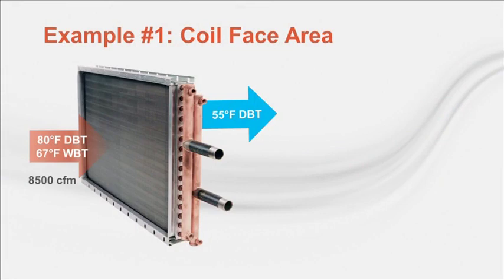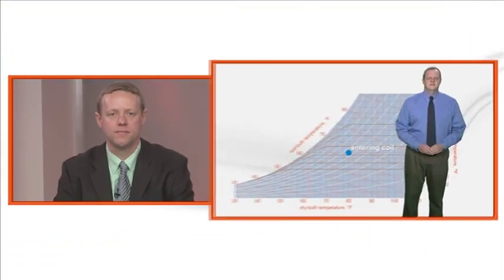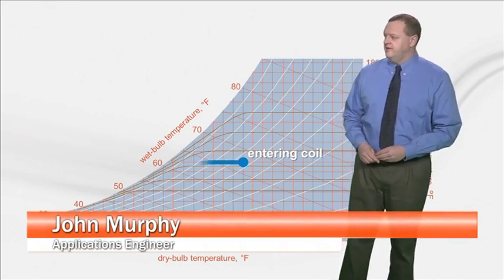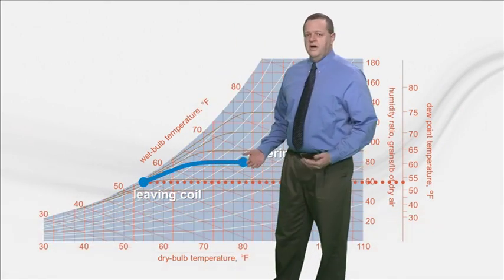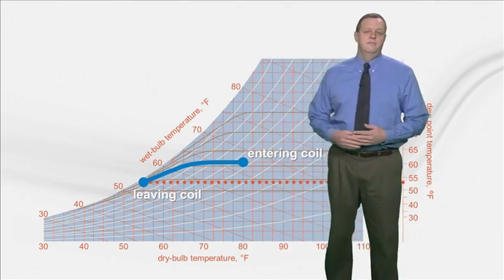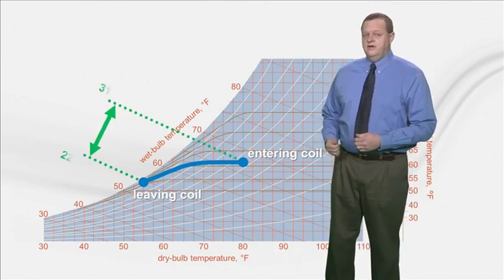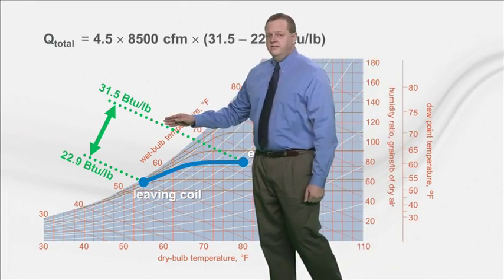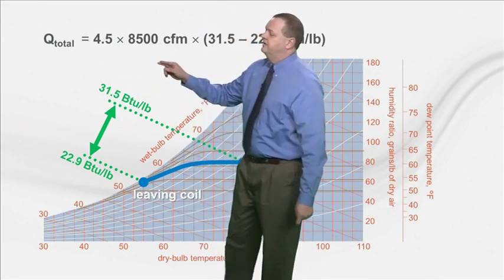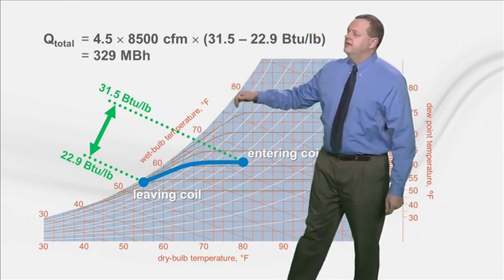For a demonstration example, the condition of air entering the coil is 80°F dry bulb and 67°F wet bulb. 8,500 CFM of air needs to be cooled and dehumidified to 55°F leaving the coil, with entering water temperature of 44°F and a 10°F temperature rise. From the entering and leaving air conditions, we can determine the corresponding enthalpies. Using the total heat equation — 4.5 times the airflow times the change in enthalpy — we calculate the total heat transferred as 329 MBH. This is the total capacity we need to select this coil to produce.